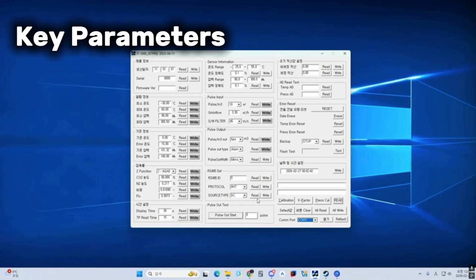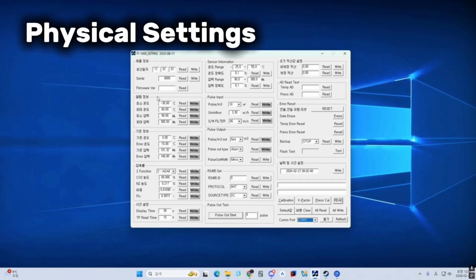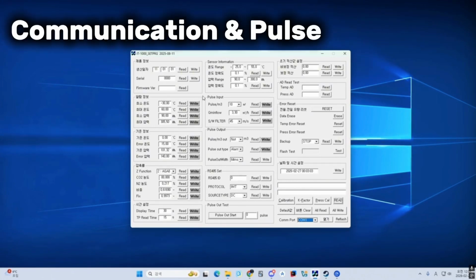Under basic information, you can check the serial number and the firmware version. In the correction settings, you can finally adjust the correction factors for temperature, pressure, and gas compressibility. You can also set the RS485 communication speed, device ID, and the pulse volume coming from the gas meter.